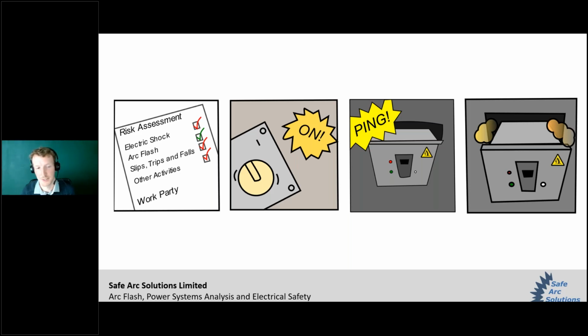So the compressor house isn't going to be starting up today, but both Sam and Scott are uninjured, and the damage to the breaker from the arc is minimal. They'll have to investigate and make a repair, but the rest of the switchboard is largely unaffected. Having the mitigations in place has prevented harm to the electricians and limited equipment damage from the arc flash.